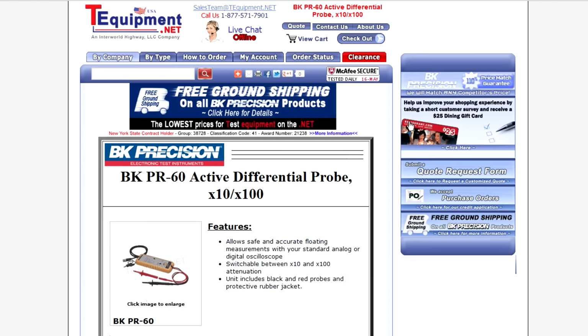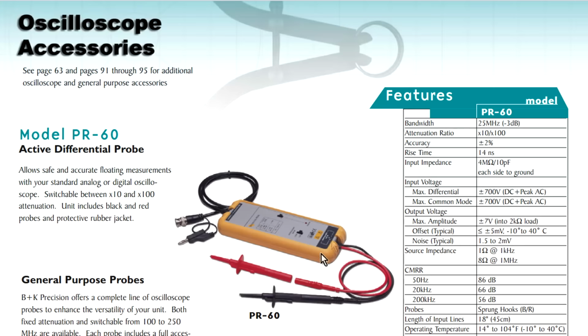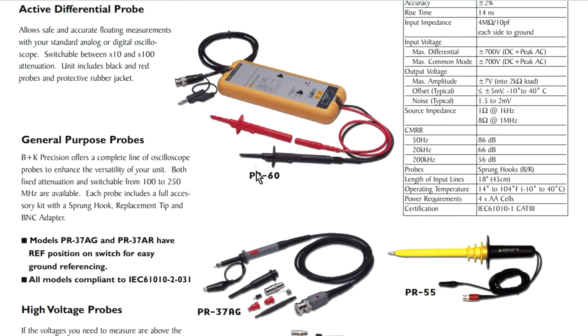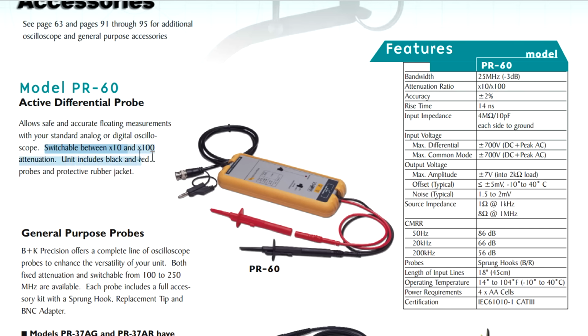PR60 probe. We're only talking $300 and something for these type of probes, and as you can see, it converts the single-ended BNC input for the oscilloscope through to an isolated differential probe system like this. So you can put positive and negative anywhere in any product at all, mains earth referenced or not, and it'd be completely safe. And usually these probes are actually high voltage probes, so they'll actually have a times 10. So this one's switchable between times 10 and times 100 attenuation, so it actually replaces your traditional times 10 single-ended oscilloscope probe.